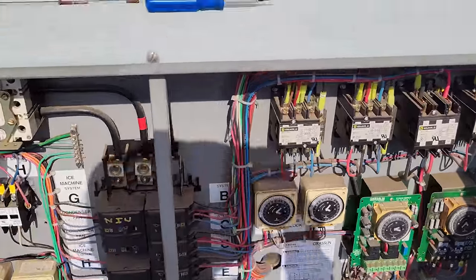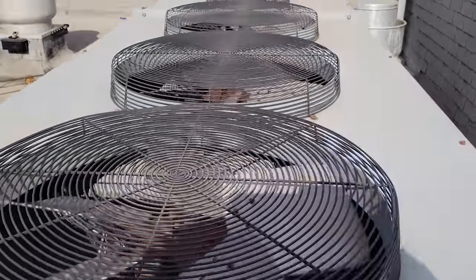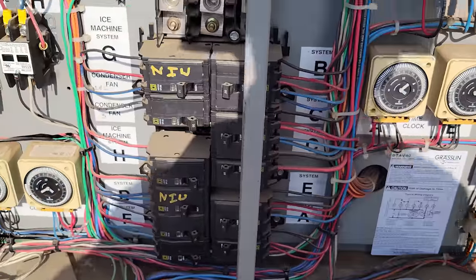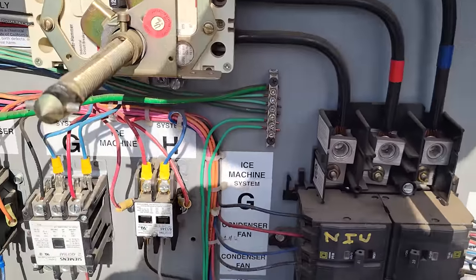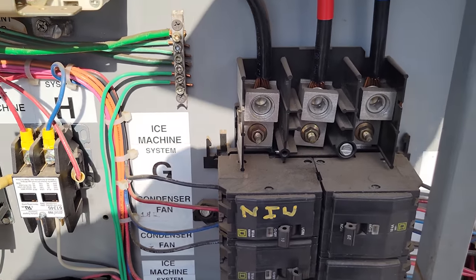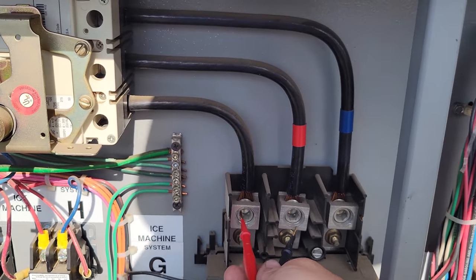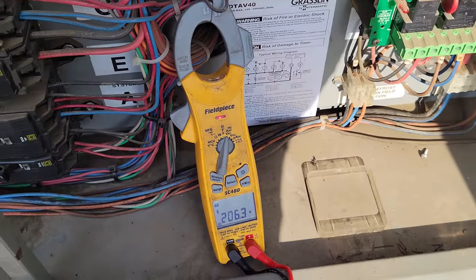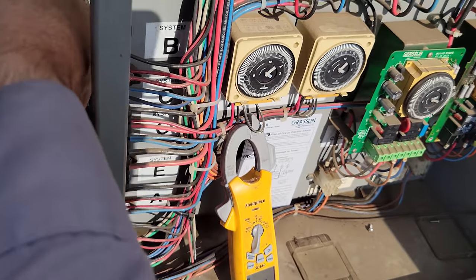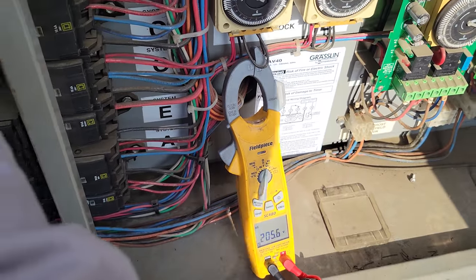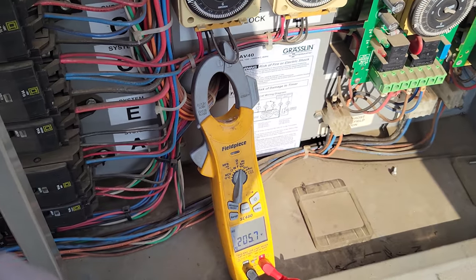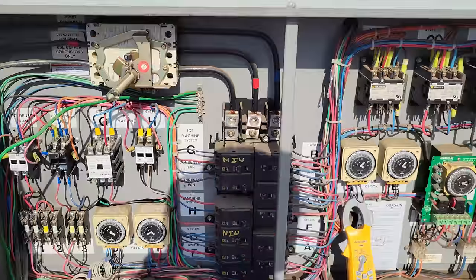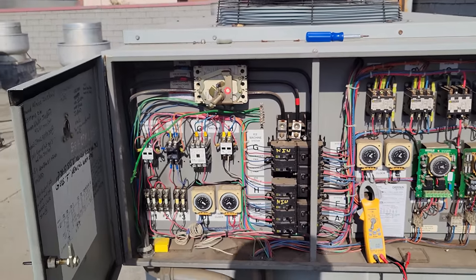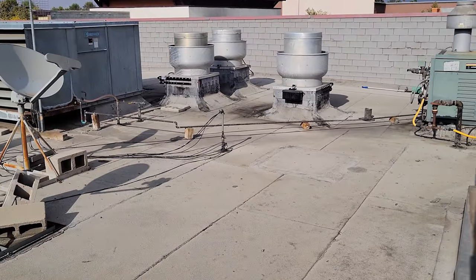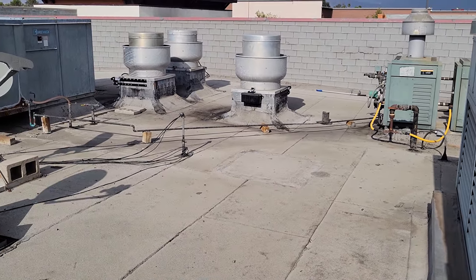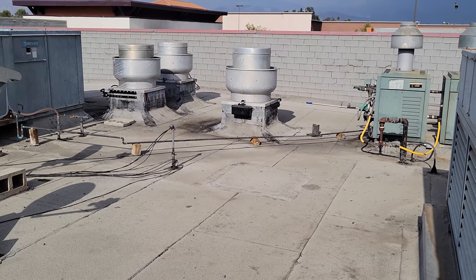Well, I get up onto the roof and everything's running. All the condenser fan motors are running and we have three-phase. Well, I'm assuming we have three-phase power up here. Let's check. So, I don't know what they mean that refrigeration equipment's down. 206, 205, 205. So we have three-phase power coming into the rack. This is all their compressors for everything, but we don't have any exhaust fans. So yeah, we're gonna have an issue downstairs.